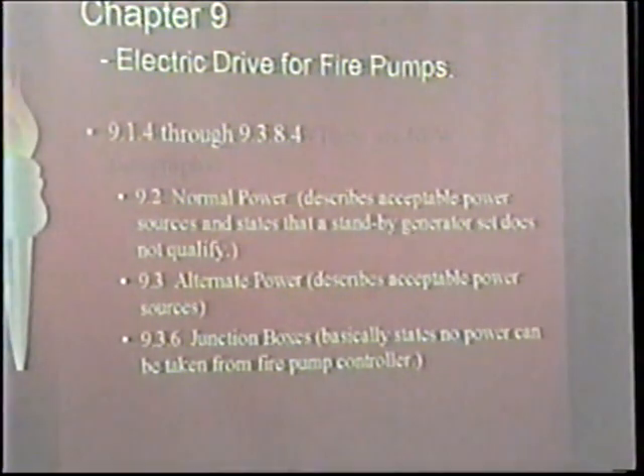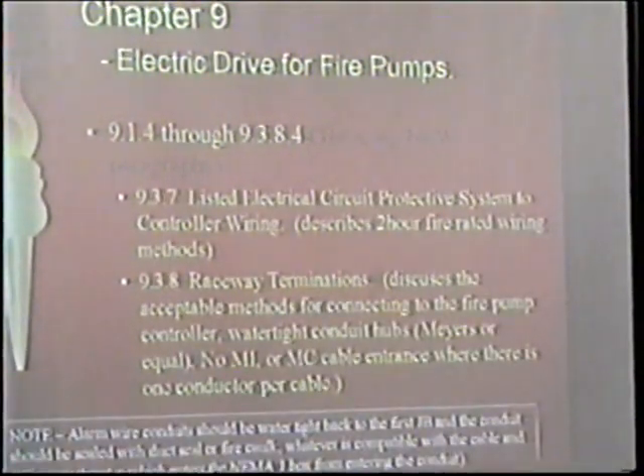Junction boxes. We've had issues in the past where some people decide they need to run a loop or something, and they're going to tap power off of the fire pump controller. They're going to tap power out of it to go to the jockey pump controller. It's not a junction box. The only wires that are allowed coming in there power-wise are the three-phase wires coming in, and the wires going out to the motor. They can't draw voltage out of that box to go anyplace else, unless it's an approved fire pump accessory circuit, i.e. a remote alarm panel, something like that.